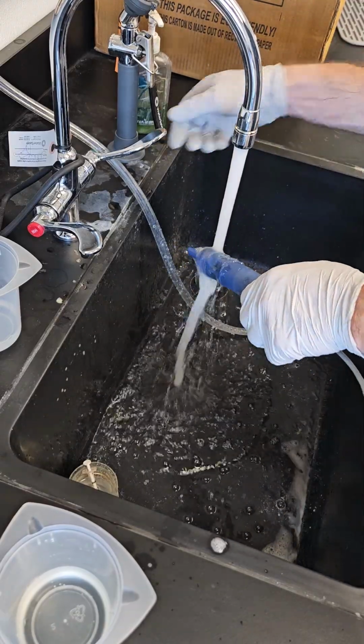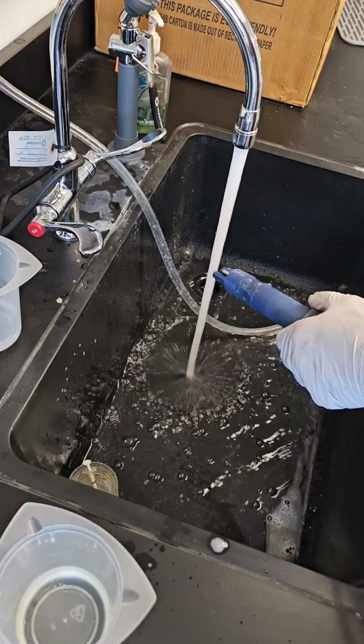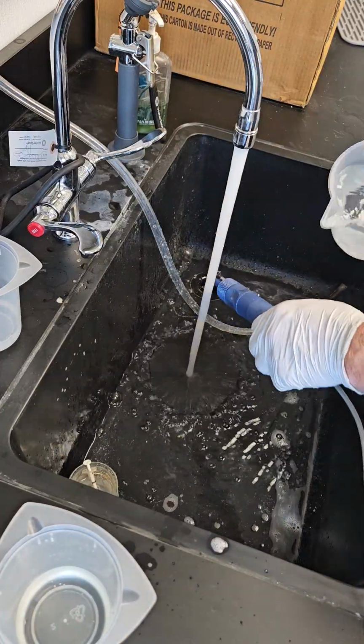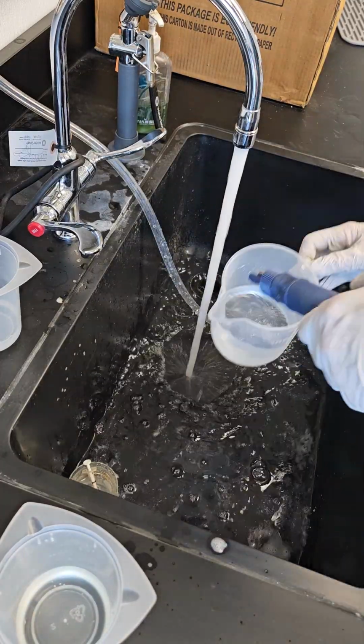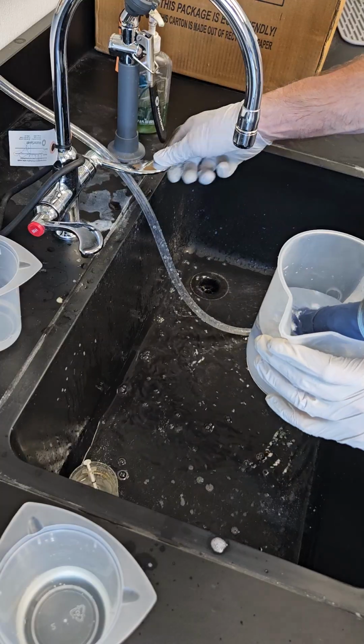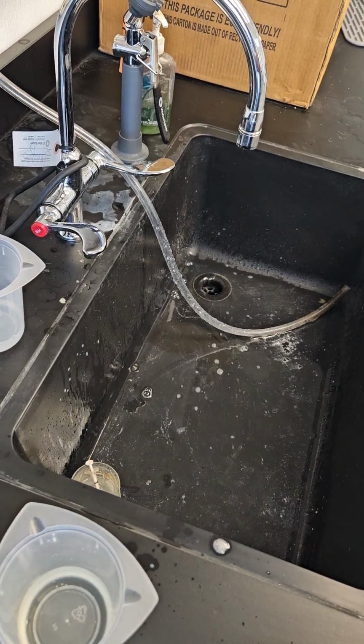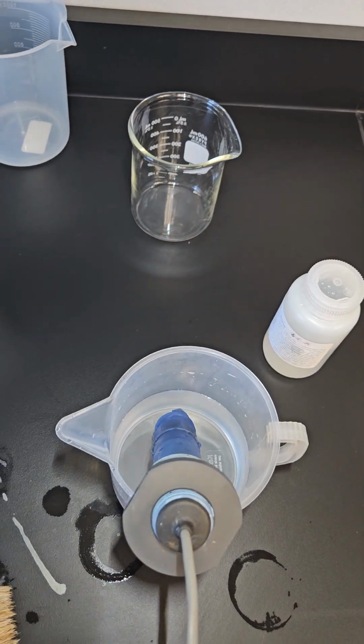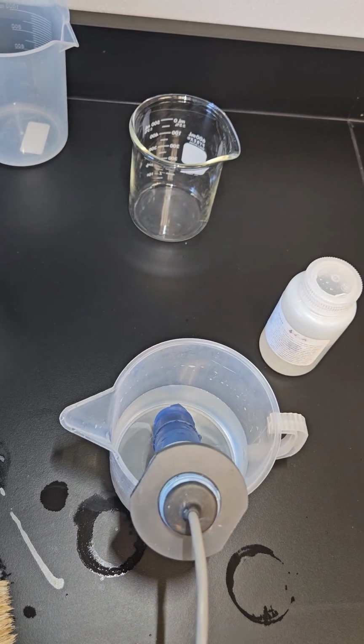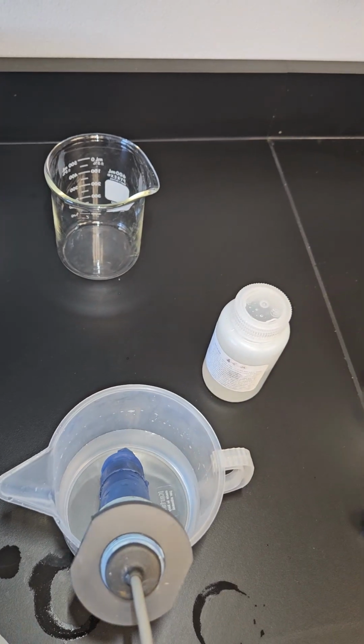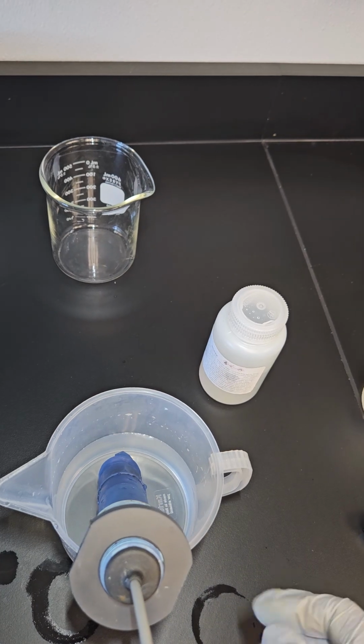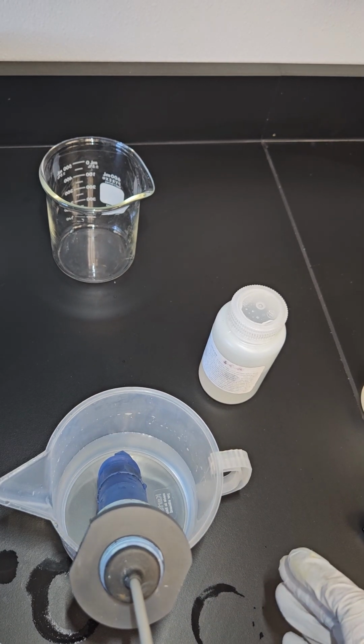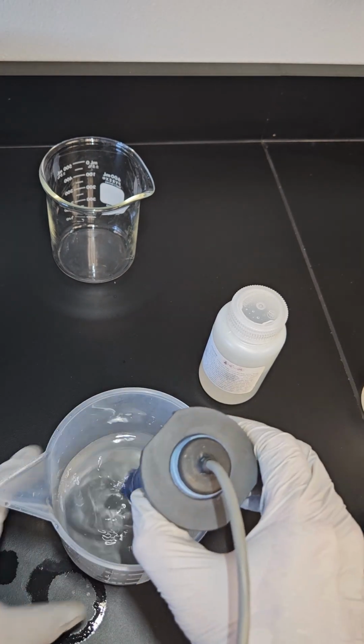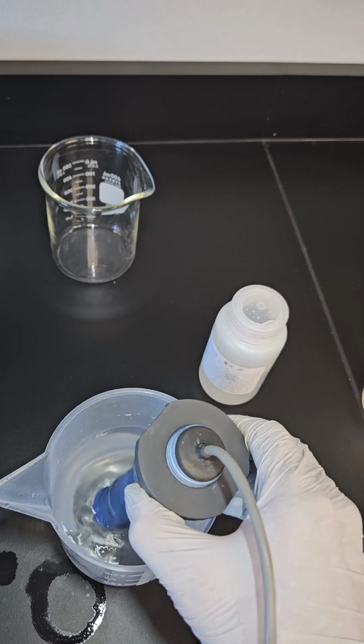Okay. And it really needs to be dunked in water after an acid wash. So this is clean water here. I'm going to put it back in clean water and soak it for a good 5 minutes. If the probe is connected to the meter, you should be able to look at the pH on the meter and see what reading you're getting.